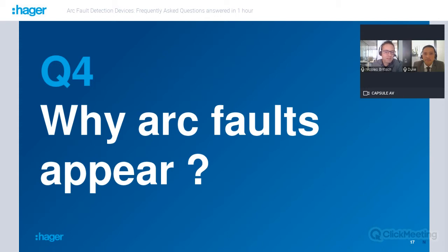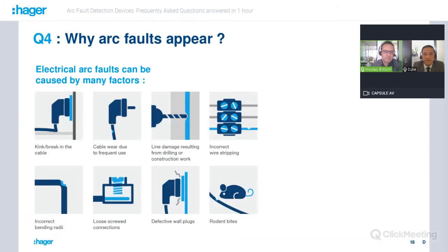Okay, now that we know what arc faults are, Duc, can you tell us a little bit more about why arc faults appear? Okay, we can see different factors. We can see a kink or break in the cable, wear due to frequent use, or cable damage resulting from drilling or construction work. We have incorrect or bad bending or damage while stripping, or loose screw connections. Or after time, we have defective wall plugs, or sometimes rodent bites. So all of these factors damage the wiring, the system, the products, and create the opportunity for arc faults. And then from arc faults, it can create bigger damage like electrical fire.